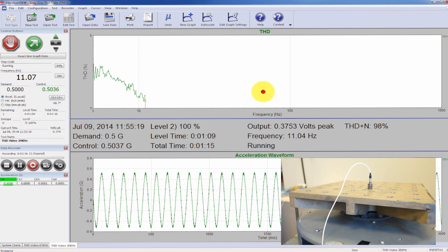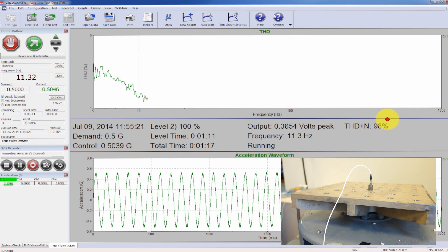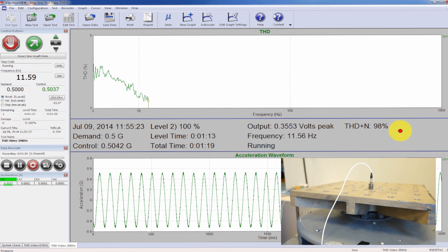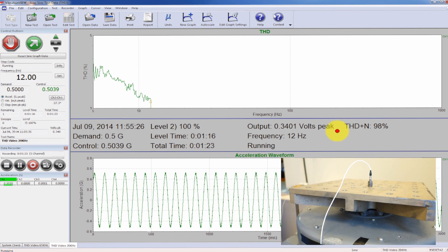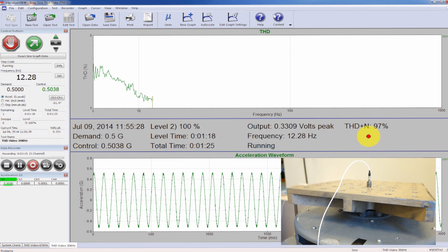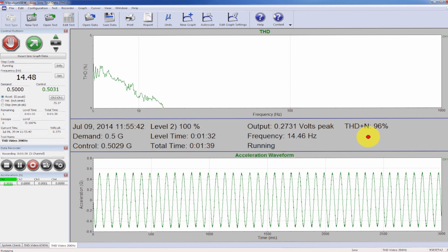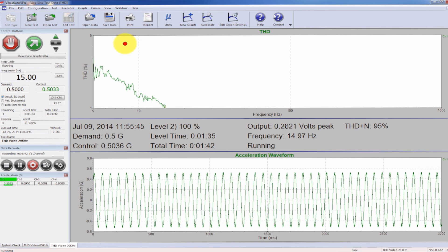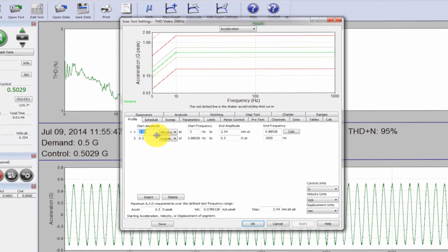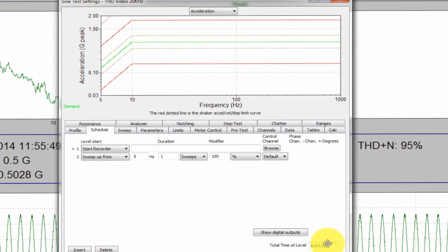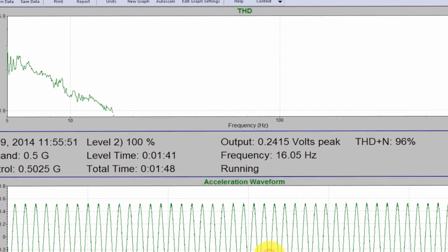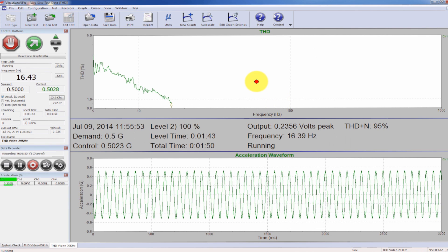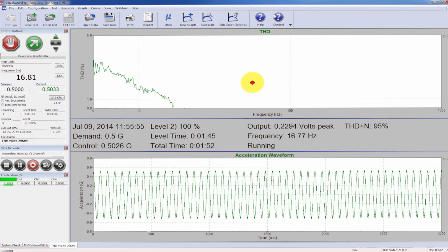You can see on my text window right here, I'm calculating THD plus N. And that calculation is currently at 98%. So this sweep is going to take some time. If I click edit test, we can see exactly how long it's going to take. It's going to take about seven minutes. We're going to go ahead and let this run.